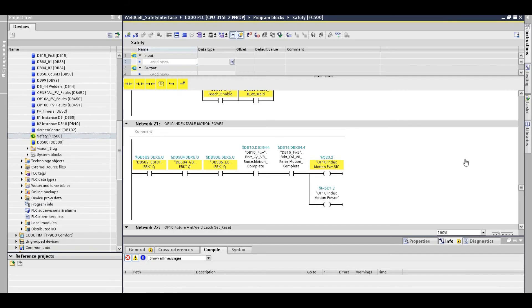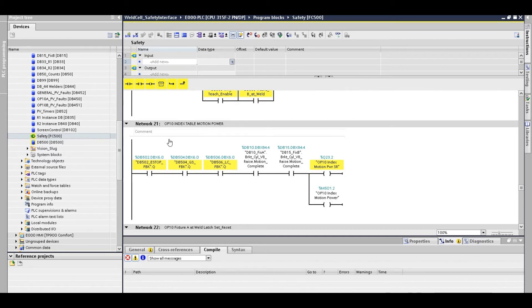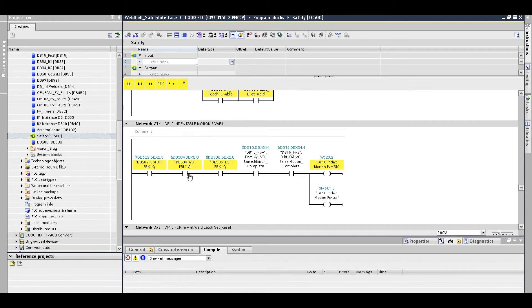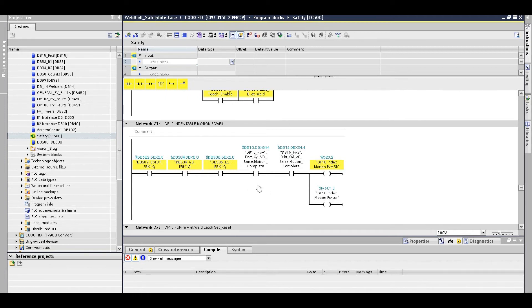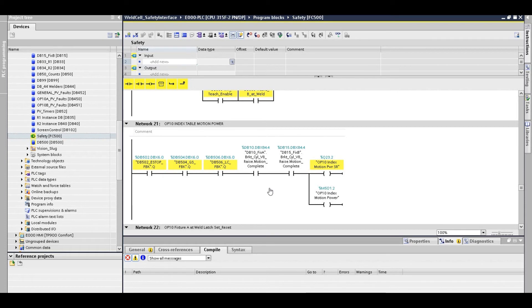In my case, for example, this is the safety program. This controller is an S7-315 safety controller. In this safety logic, control this index table enable. Other than the e-stop, gate switch, and light curtain clear, the signal is still waiting for these two normal statuses. These two statuses come from two normal DB. This is an existing project programmed by others before. I used these two DBs to add some cylinders.